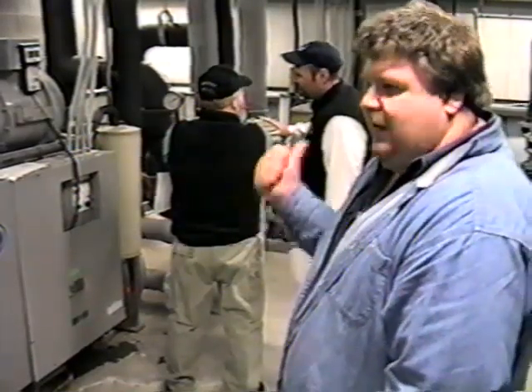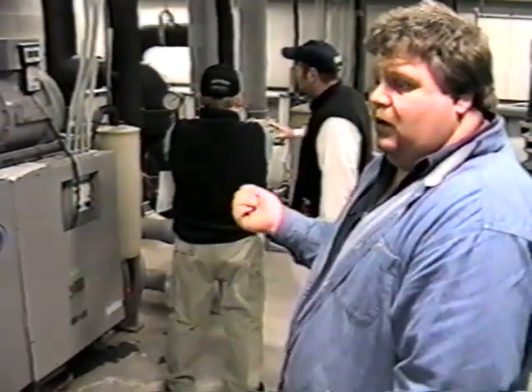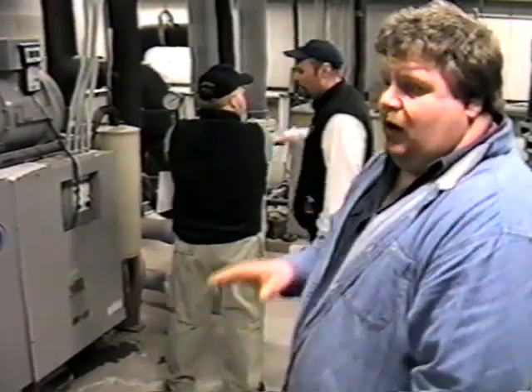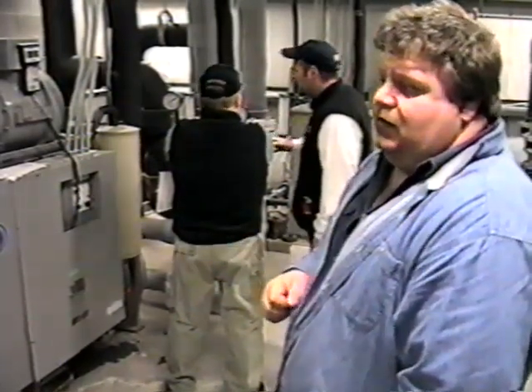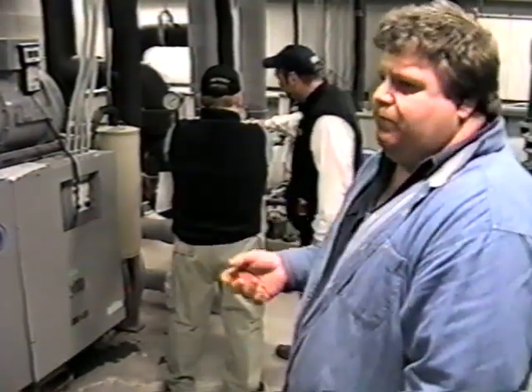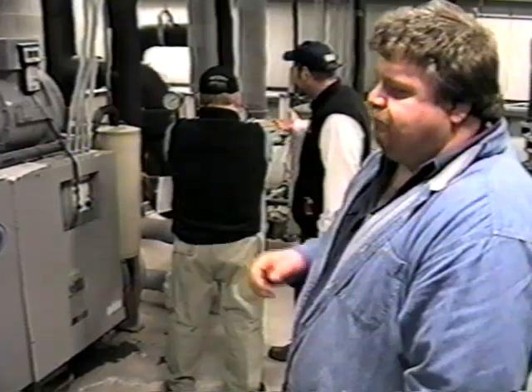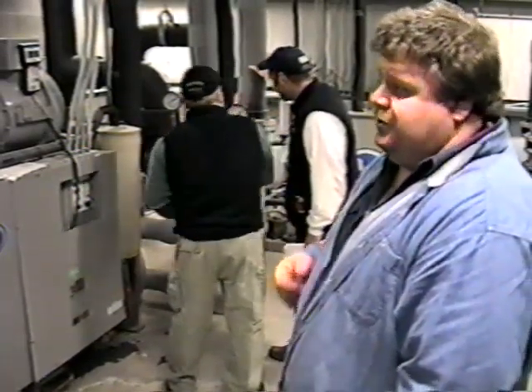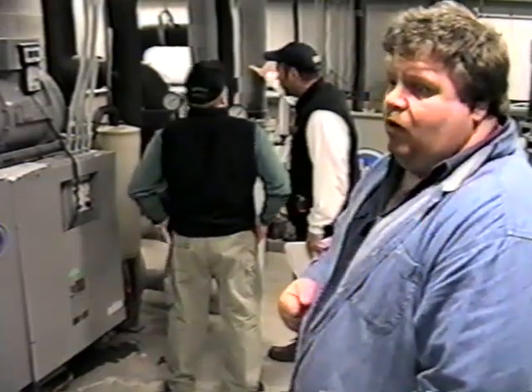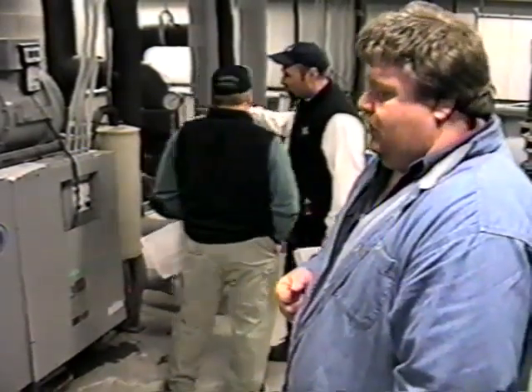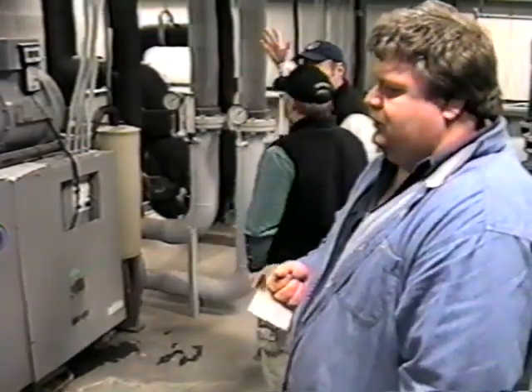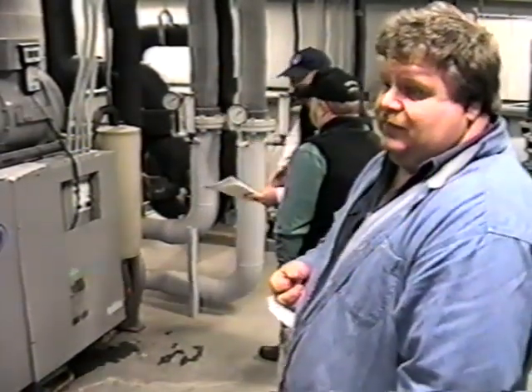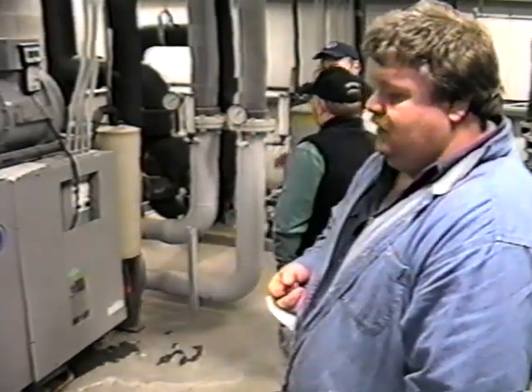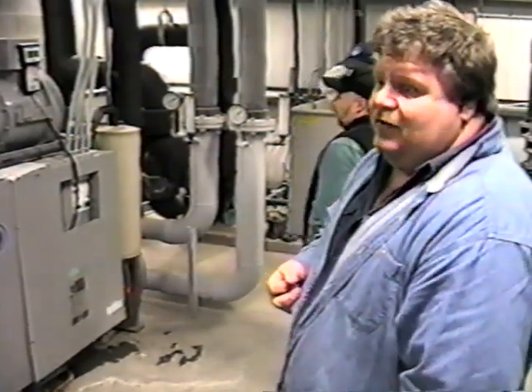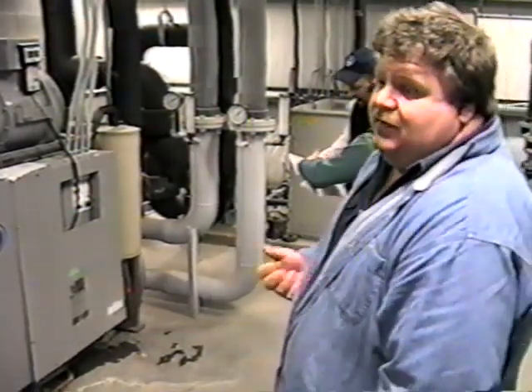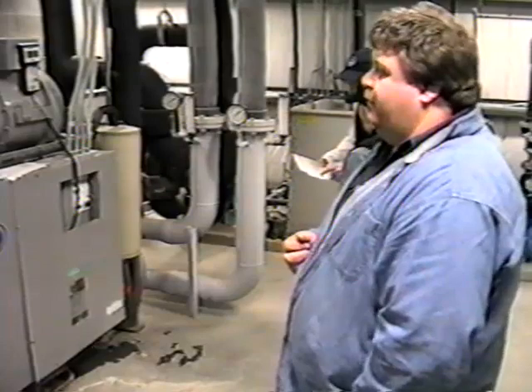That's unlike maybe on the other side, where there are times the oil wasn't cleaned up on the deck. I always recommend that the deck be cleaned, not only by the service people, but by the management. They should keep it clear, so that you know when something new is happening, that you sprung a glycol leak or a freon leak. So like I say, a lot of this doesn't take a refrigeration guy to figure out there's stuff going wrong. It's kind of like dealing with your car, so it's most of the same physics, as far as heat transfer and all that.